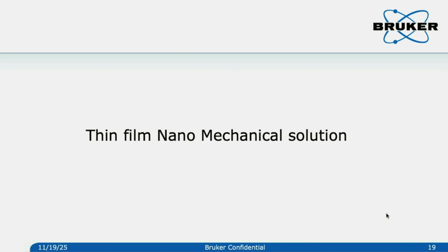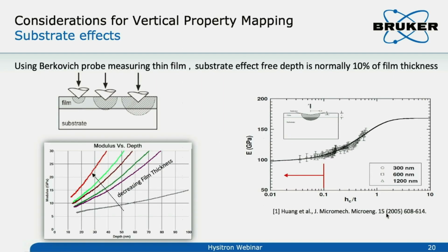Secondly, I would like to talk about thin film measurement. For thin film measurement, we know we have a challenge we call the substrate effect. This is the contact depth of the nanoindentation. This is a thin film sample. When you go deeper and deeper, your stress will penetrate over the interface and your substrate starts to deform. That will influence our hardness and modulus data. We call it the substrate effect. Typically, if we look at the papers, at the contact depth divided by the total thickness, almost 10% of the film thickness, you start seeing the substrate effect.